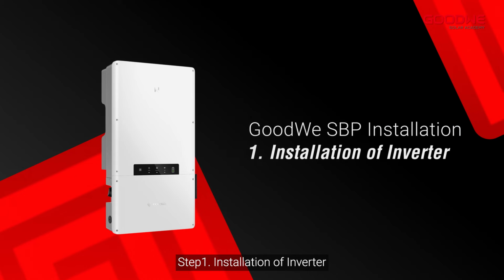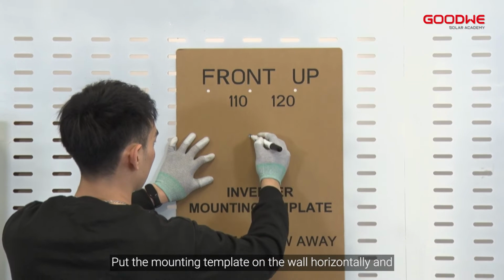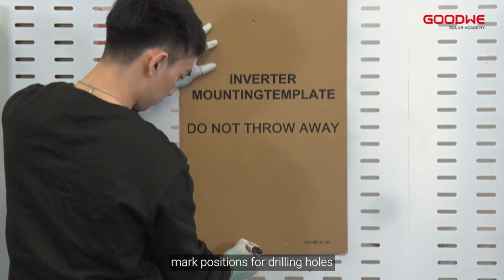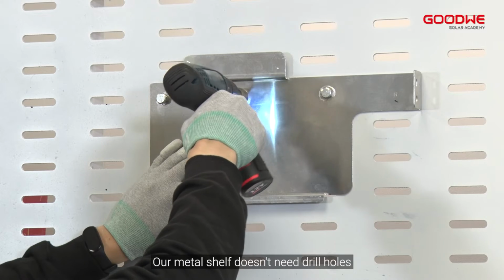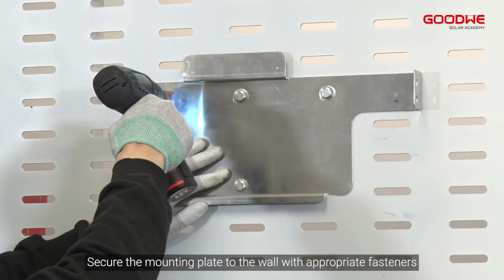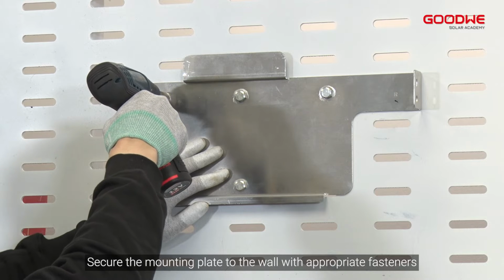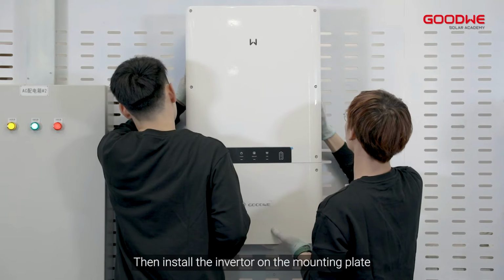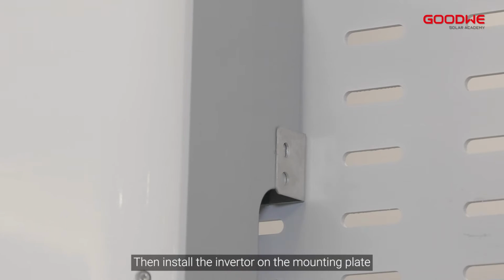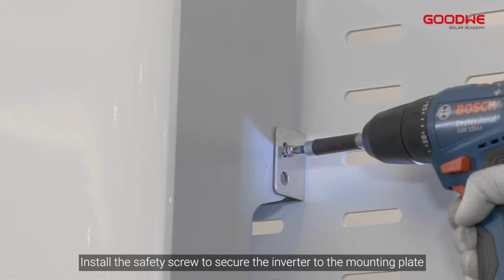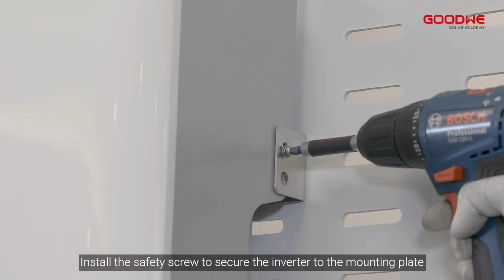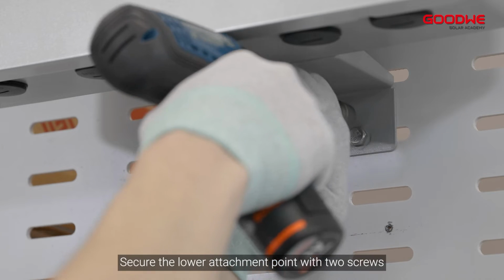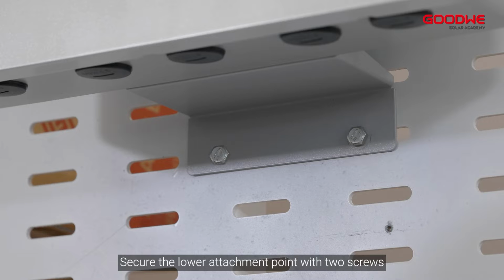Step 1. Installation of the inverter. Put the mounting template on the wall horizontally and mark positions for drilling holes. Our metal shelf doesn't need drill holes. Secure the mounting plate to the wall with appropriate fasteners. Then install the inverter on the mounting plate. Install the safety screw to secure the inverter to the mounting plate. Secure the lower attachment point with 2 screws.